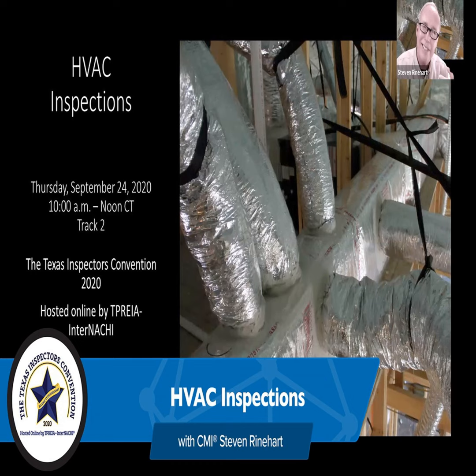In the old days, you had a vented door that would pull combustion air from the hallway. Can't do that anymore. The door, I recommend, if I see a unit in the house, in a closet, and it's got a 2-inch undercut in the door and it's got a return right below it, here's a scenario. That air handler comes on, starts sucking air. It sucks from under the door. You got maybe an atmospheric drafting furnace. It's sucking the exhaust and very efficiently sending it to all the rooms.